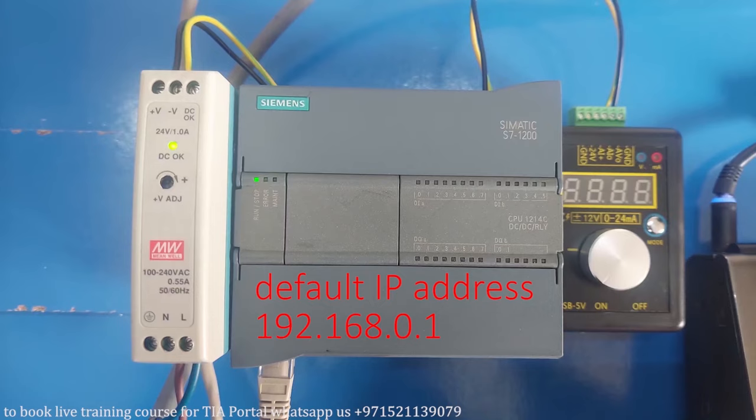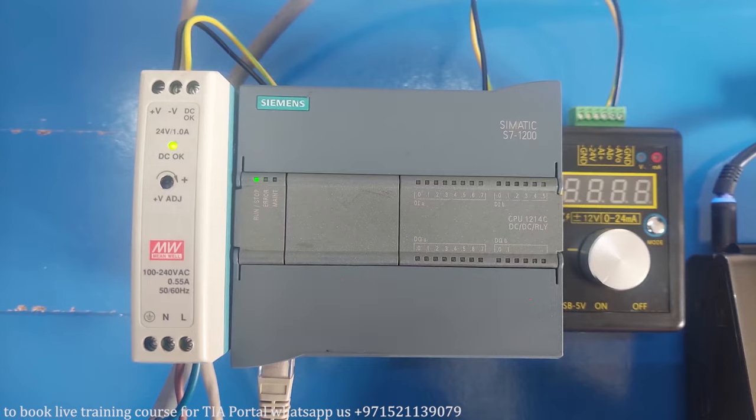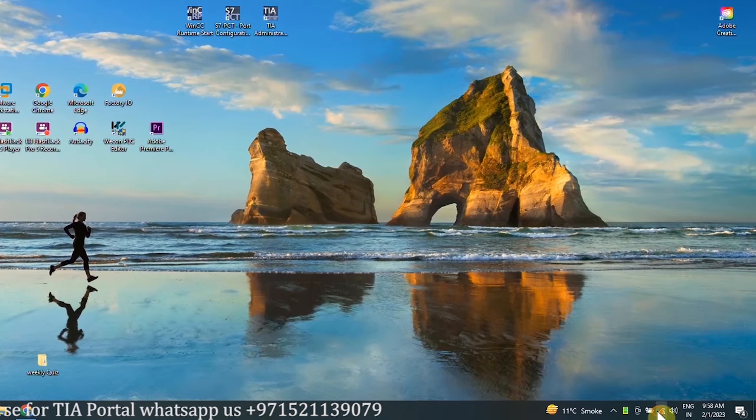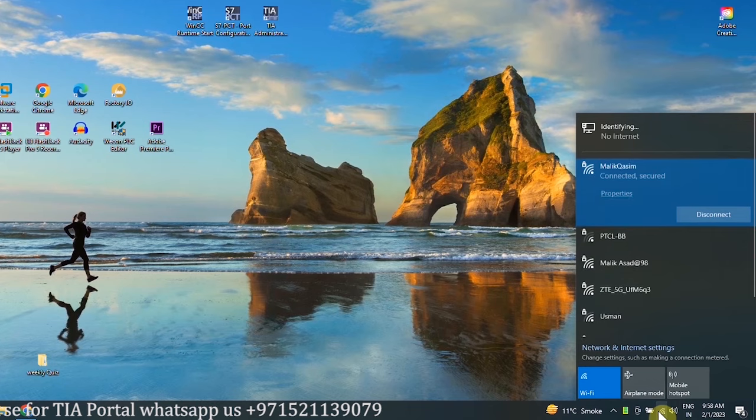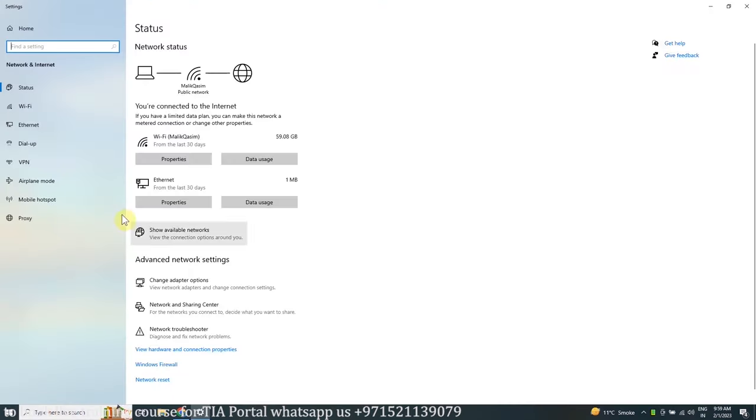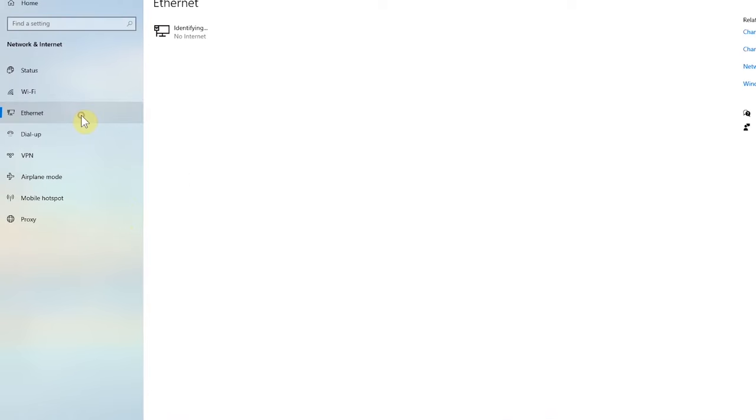By default, the IP address of S7-1200 PLC is set to 192.168.0.1, so we have to make some changes in the settings of the ethernet adapter of the PC. To do this, we will open the network and internet settings. Next, select the ethernet adapter and click on the change adapter options.